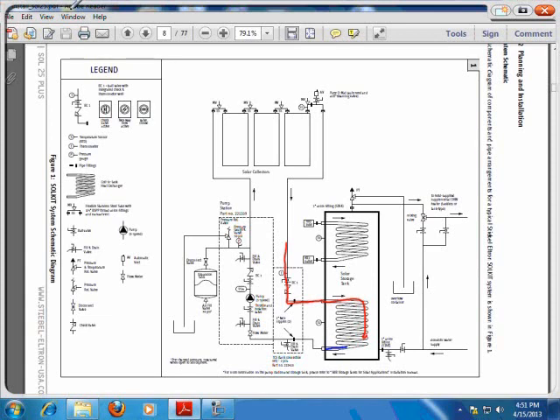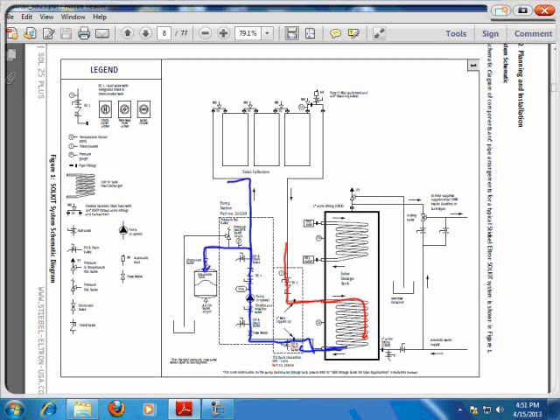I have cold water that is now coming out of my system, up through my valve body, through my flow meter that flows through. The drain valve is closed. The water flows through this valve from my pump. There's a three-speed pump. We'll talk about pump speeds when we get to the pumps. We flow out this way. At the same time, pressure is equal all throughout the system, and we're going to flow into this expansion tank. Remember that we were somewhere near that 11 to 12-gallon range setting because what that expansion tank does is as it gets hotter, that expansion tank is going to allow fluid to push that bladder down, more water stays in there, and we can keep our system at a set pressure.